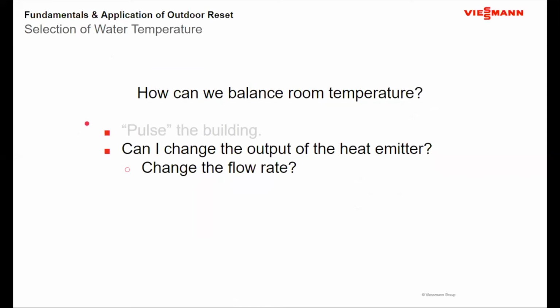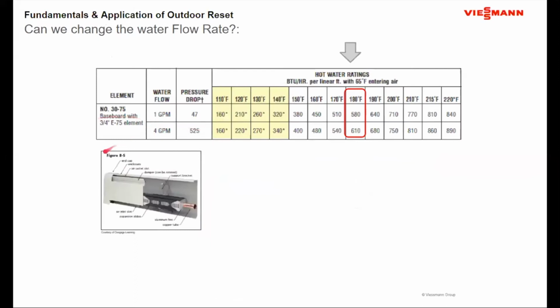Now, when that question comes up, a couple of things have to be pointed out, and the real answer is that from the ability to accurately control it, it becomes very difficult. Okay. Let's go back to our heat emitters and take a look at the performance numbers. I'm still going to concentrate on 180 degrees, but I want to look at two different flow rates here. One is at 4 gallons a minute and one is at 1 gallon per minute.